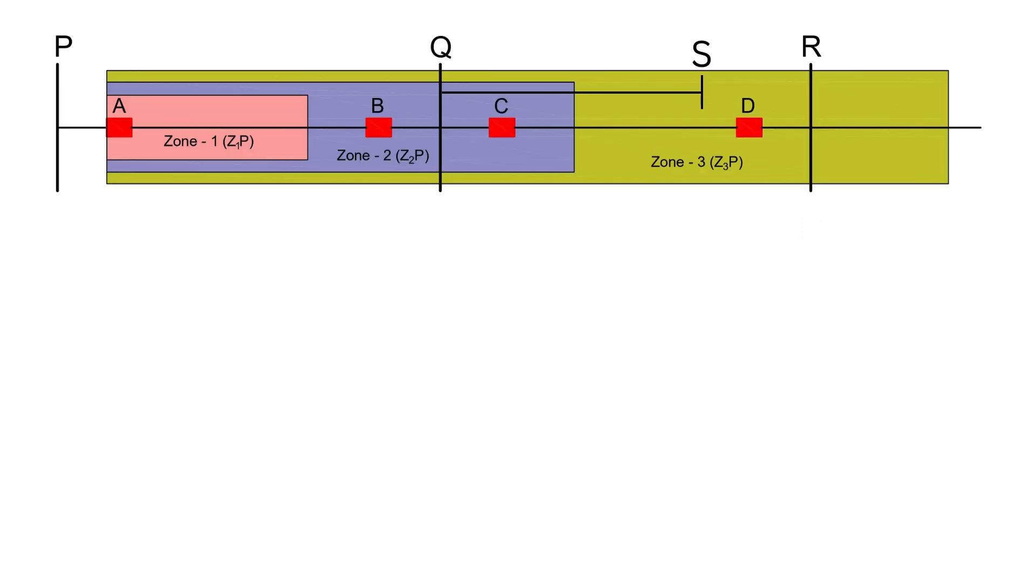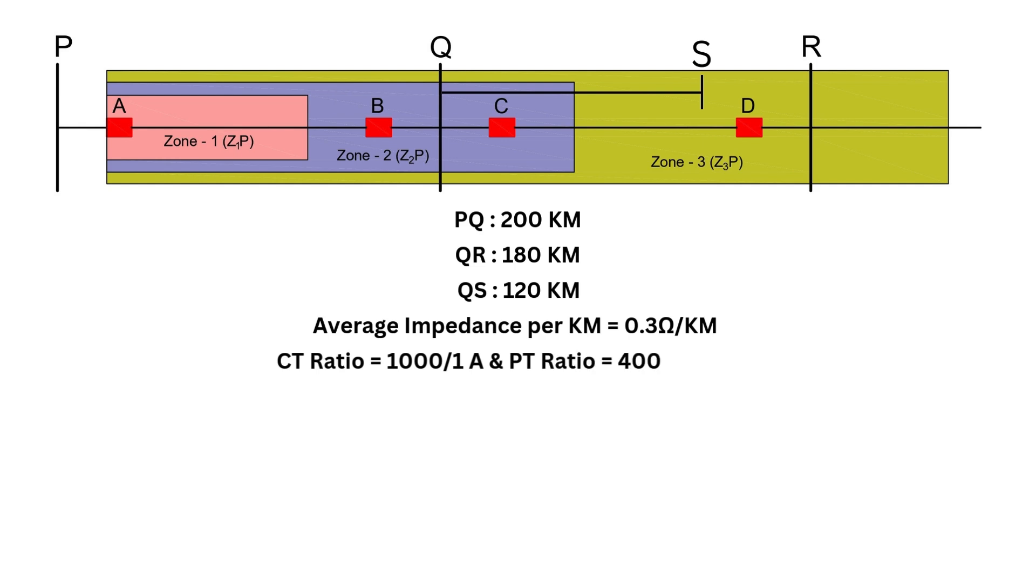Now, let's plug in some values for our calculations. Distance from P to Q, 200 kilometers. Distance from Q to R, 180 kilometers. Distance from Q to S, 120 kilometers. Average impedance per kilometer, 0.3 ohm per kilometer. CT ratio, 1000 by 1 ampere. PT ratio, 400 kV by 110 volts.